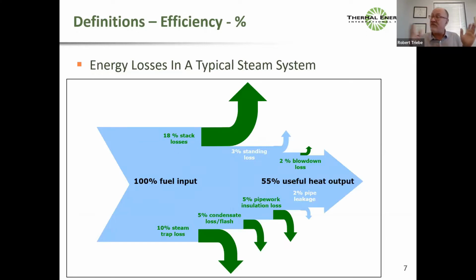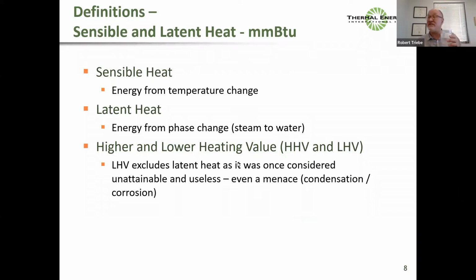Here's a Sankey diagram for a typical boiler showing 100% fuel input. This would be for a natural gas boiler where we have 18% losses in the stack. So that would be an 82% thermal efficiency. But as we know, we lose energy in steam traps, condensate, pipe work, insulation, blowdown, standing losses, pipe leakage. So typically, most people who use steam systems would agree the amount of heat that reaches the end user is between 55, this might be on the low end, but between 55 to 70% of the heat actually gets delivered to the end user, and the rest is lost and wasted in the system. So quickly, I'll define sensible and latent heat.